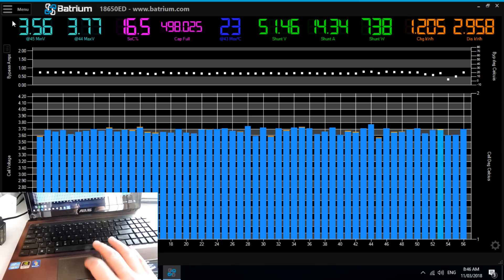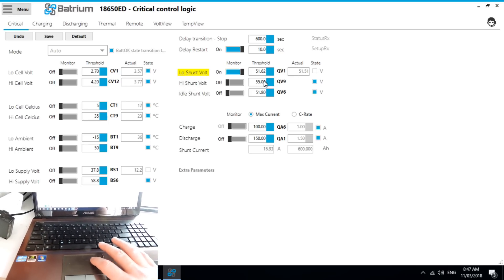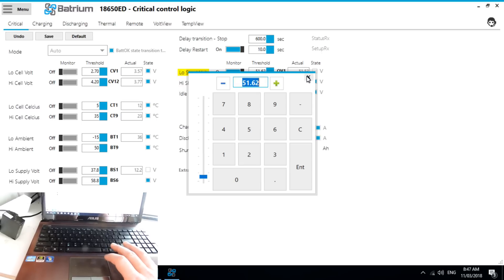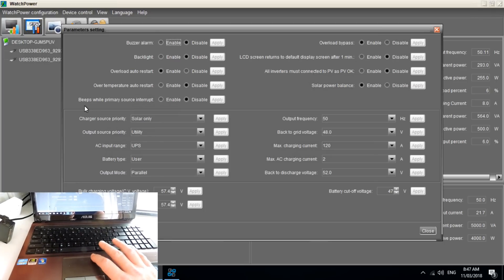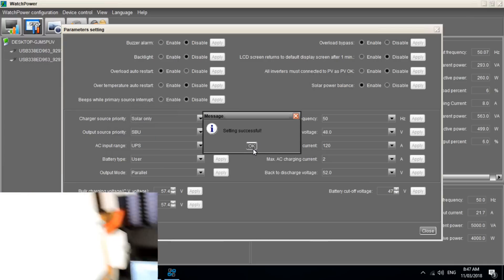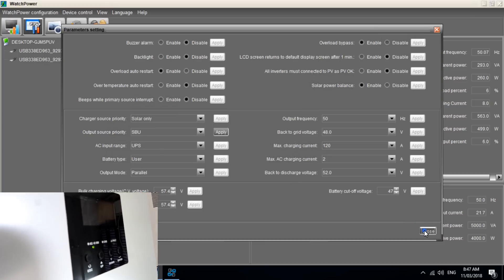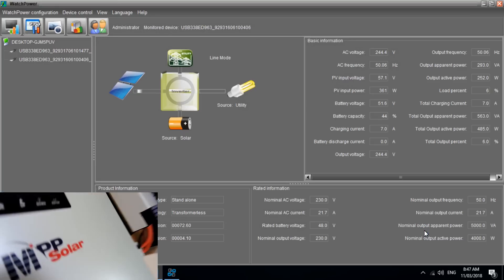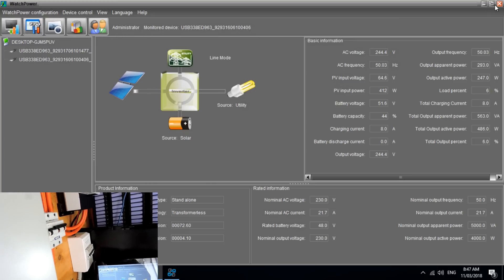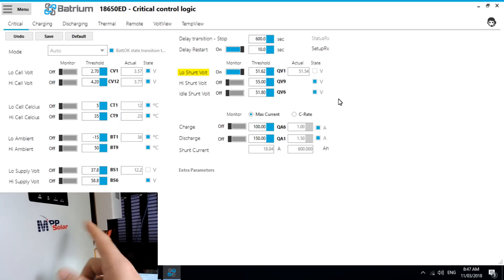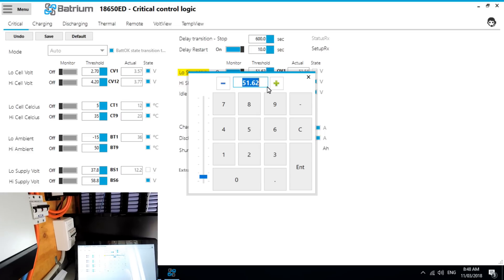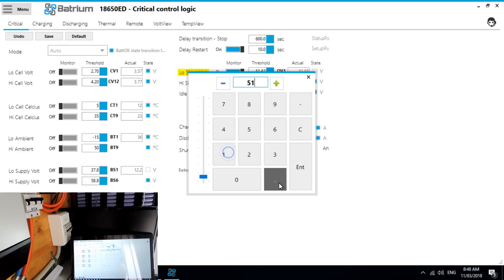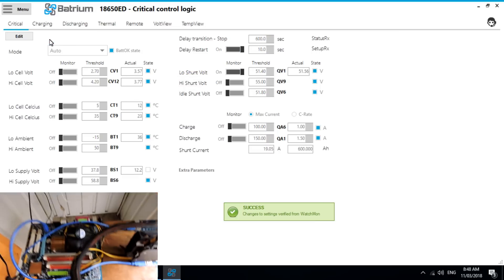Now if we want to turn it back off again, so in the morning when we need to turn it back off, we go back to menu, go to control logic. Now we want to turn back off again. We've got 51.62, so we change that to just below. If we leave it there and then turn a load back on again, turn it back to SBU, apply. We should hear a click up here. It does take a few seconds to change back. It's saying load line mode on the computer, you hear a little click once it clicks back. It can take up to 10 minutes to click back if you've been playing with it. You can't just change settings backwards and forwards and expect it to happen instantly. We might change that voltage to 51.40 volts, enter, save.